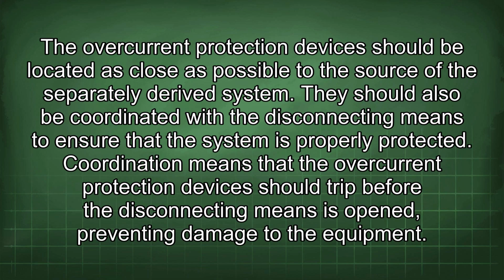The overcurrent protection devices should be located as close as possible to the source of the separately derived system. They should also be coordinated with the disconnecting means to ensure that the system is properly protected. Coordination means that the overcurrent protection devices should trip before the disconnecting means is opened, preventing damage to the equipment.